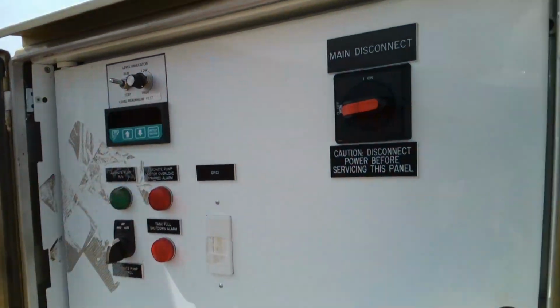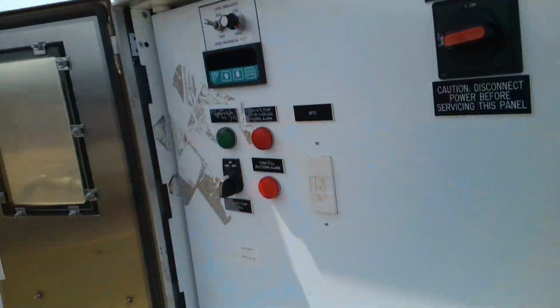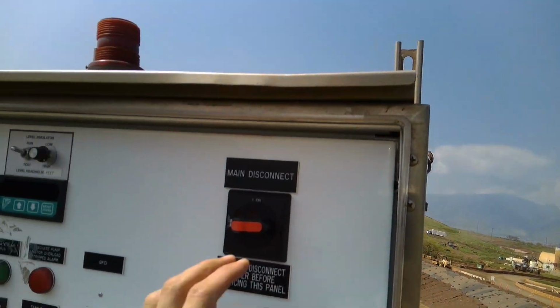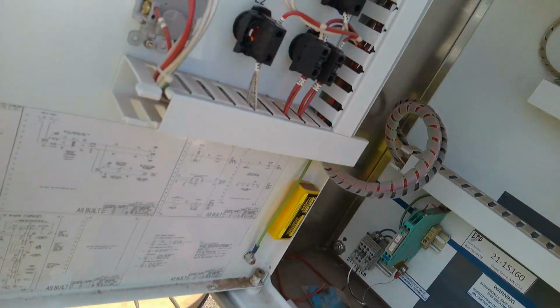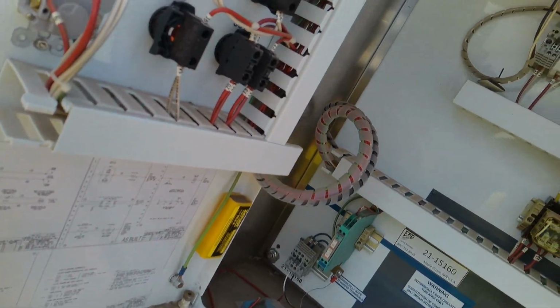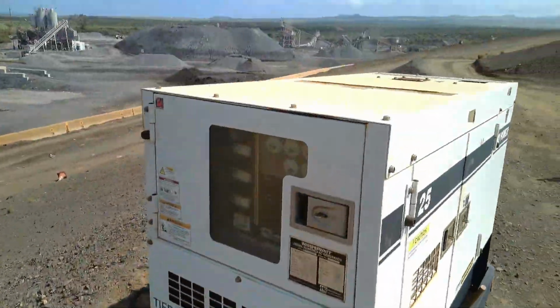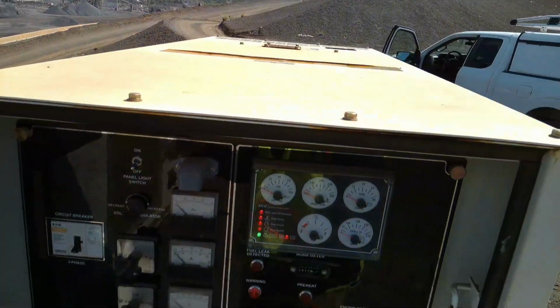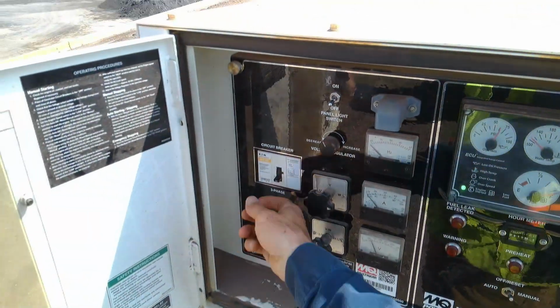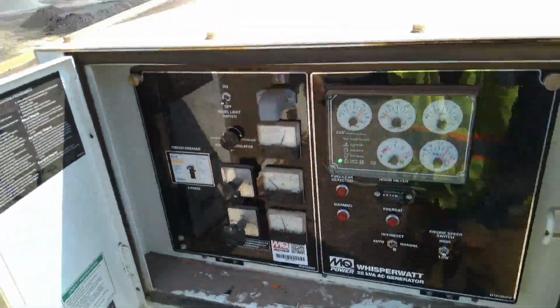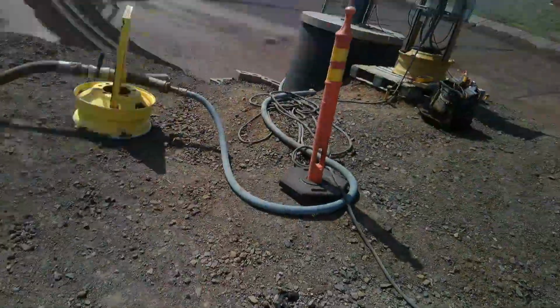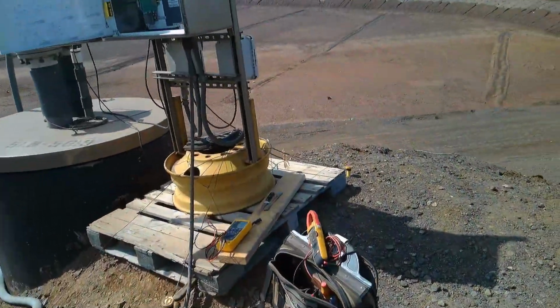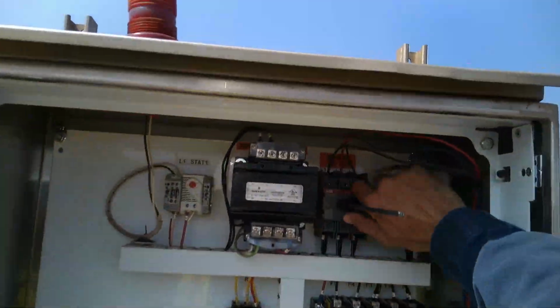So I said, well, there's only one more test I can do, because I've already used the potentiometer to simulate a higher level. But now I'll just hook in my 789 and generate a level right on the transducer input terminals. And we'll see if that works. So here we go. Fire up the gen. Fire up the panel.